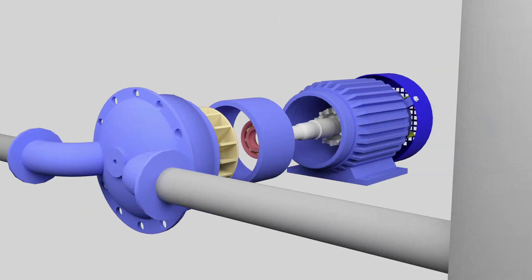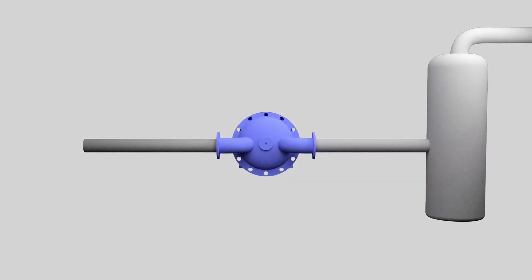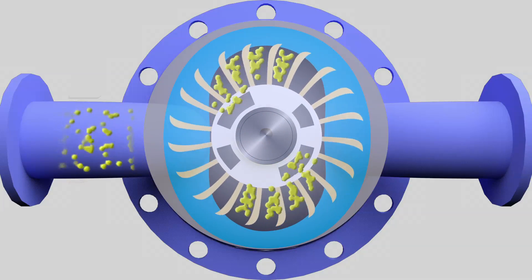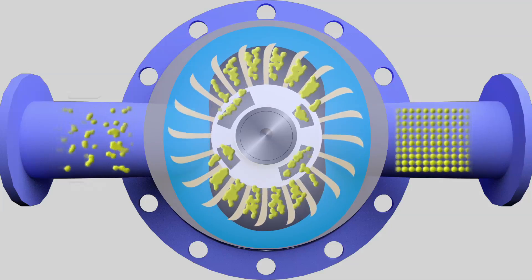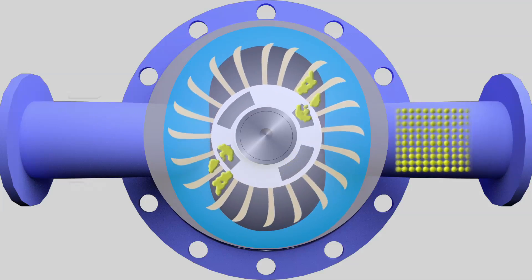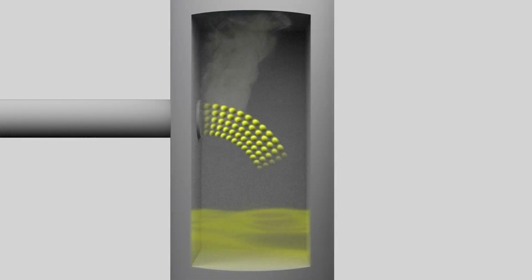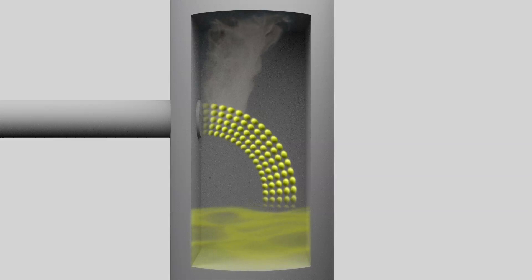The vent gas coming from the flare process unit enters into the liquid ring compressor along with sealing liquid, where it gets compressed. The compressed gas along with sealing liquid is then discharged into the water ring separator, where the gas and sealing liquid are separated. The processed gas escapes from the water ring separator through its outlet nozzle.